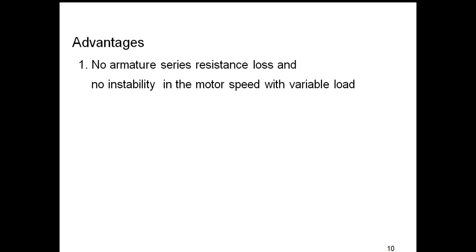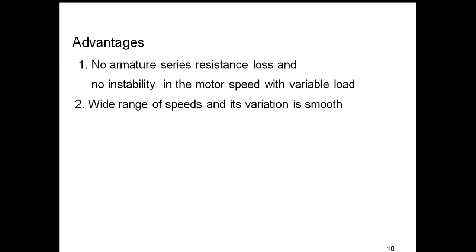Now let us see the advantages of this Ward Leonard method. Here no armature series resistance and good stability in the motor speed with variable load, and a wide range of speeds can be achieved, and smooth variation can be done.